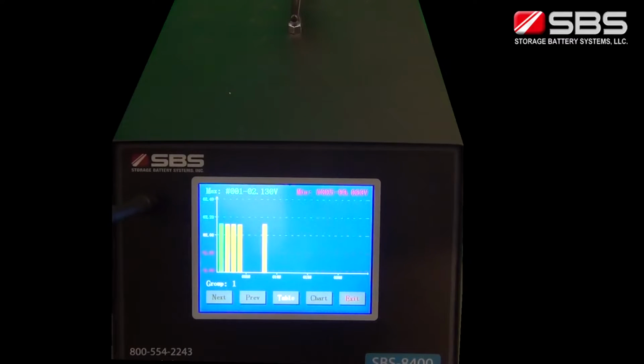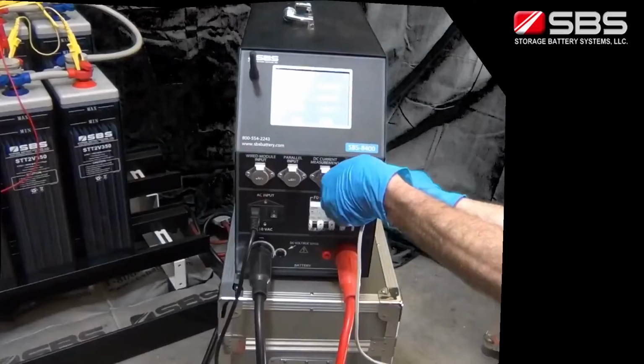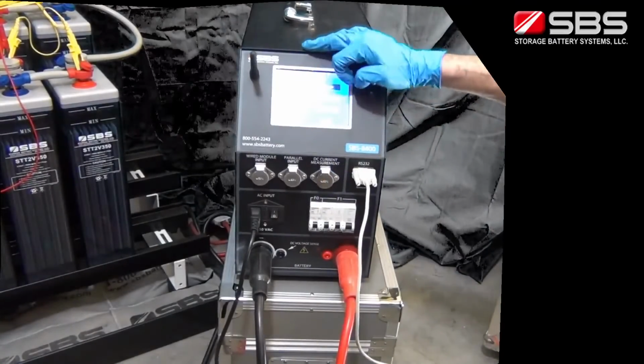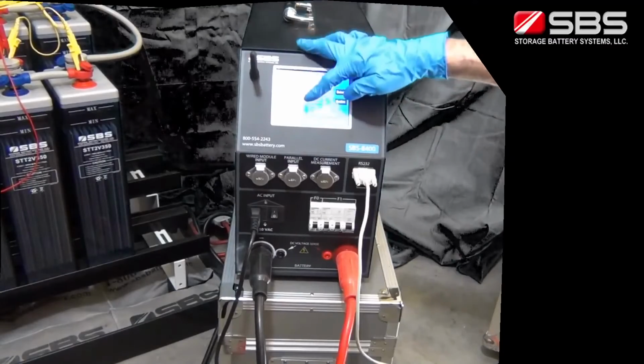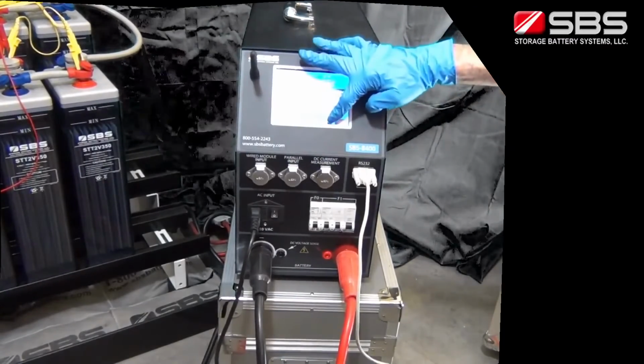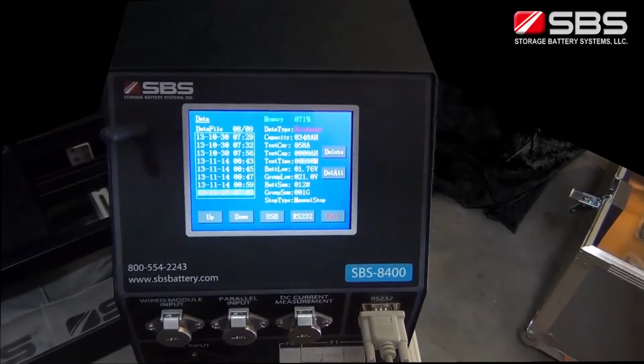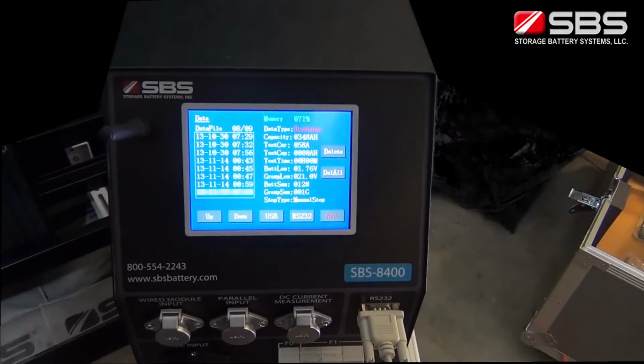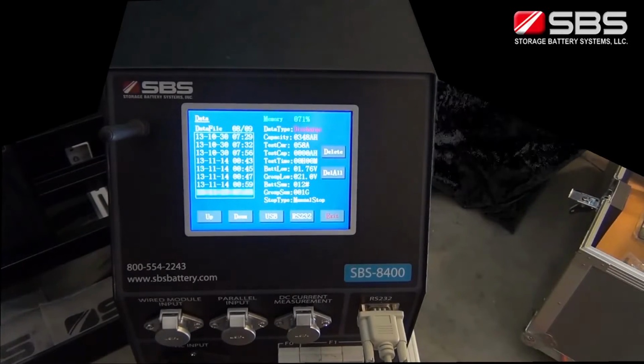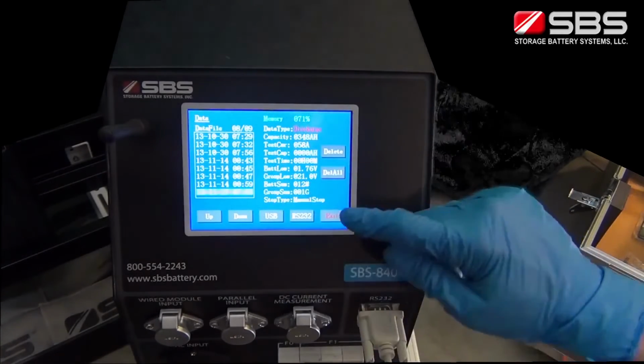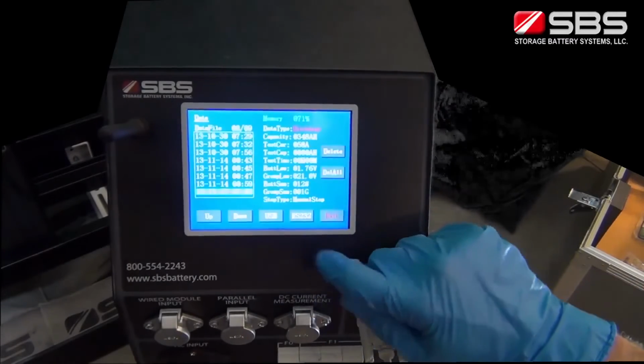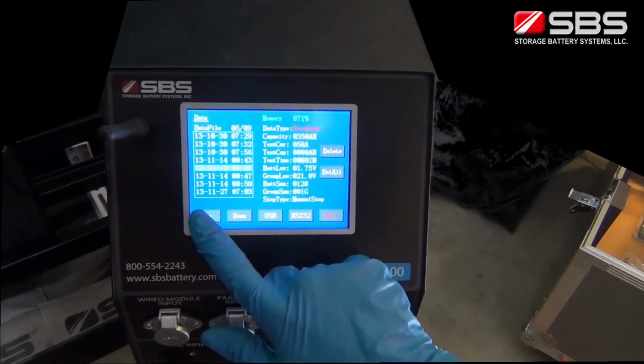On the main menu, select the battery view interface. If all wireless modules are connecting correctly, you will see the voltage of each battery displayed. If the voltages of some batteries are not showing correctly, check the wireless module's connections. The SBS-8400 provides 2 ways to record test data. You may use an RS-232 cable to connect the main machine with a PC. Through the analysis software, real-time test data is displayed and recorded during the test. The SBS-8400's internal memory also always saves all testing data. You can download the data later by USB disk or the RS-232 cable to the PC.